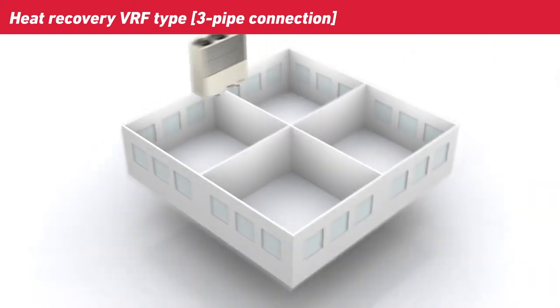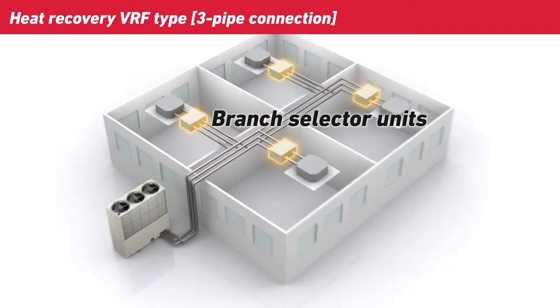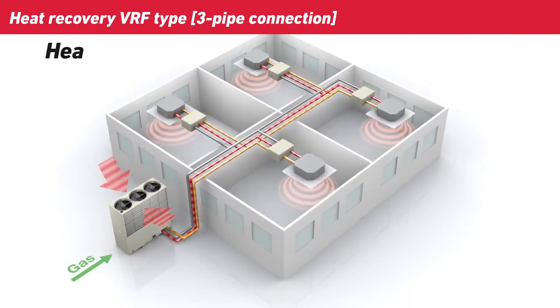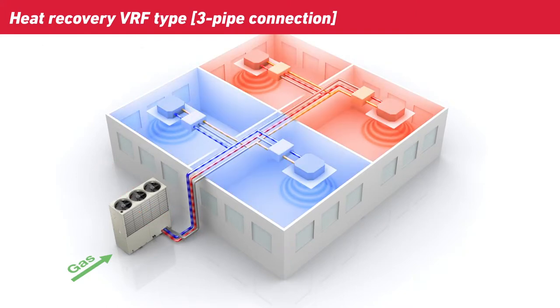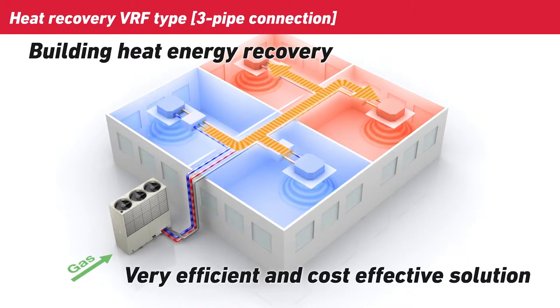Heat recovery VRF type GHP systems have an additional third pipe connection from each outdoor unit and connect to indoor units via branch selector units. These branch selector units are used to direct the flow of refrigerant in the system and allow a single GHP system to provide heating and cooling in different areas at the same time. When there is demand for heating only, the indoor units operate in heating mode. When there is demand for cooling only, the indoor units operate in cooling mode. However, when there is a mixed demand, the Heat Recovery VRF GHP system can provide both by moving heat energy from cooling areas to heating areas. This greatly increases system efficiency and reduces both the load on the outdoor unit and running costs, offering a very efficient and cost-effective solution.